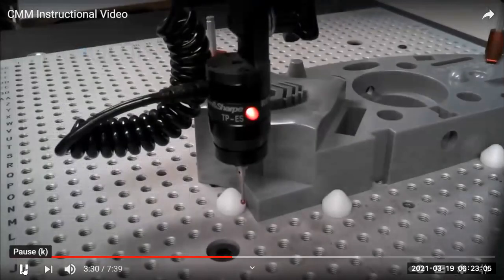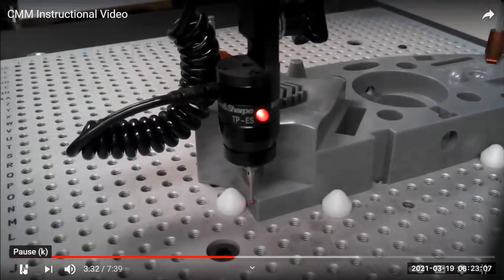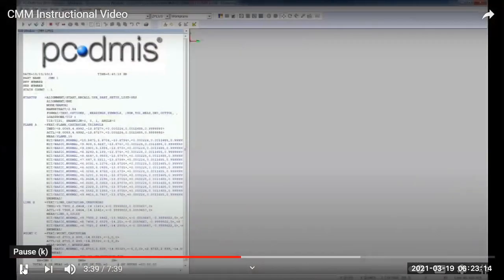To create a point, use 1 hit on any surface, then press Done. A computer alignment must be created to position and fix the part in 3D space by eliminating all 6 degrees of freedom: translation in X, Y, and Z directions, and a rotation about each of these 3 axes.